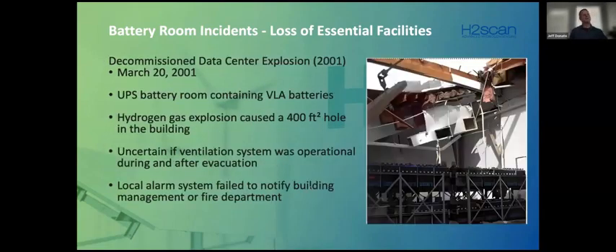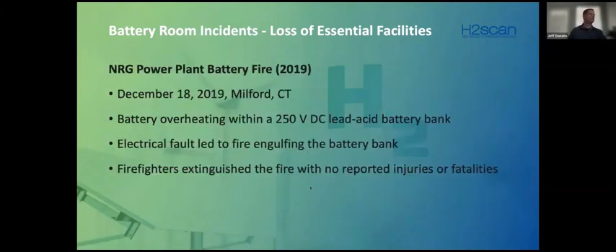Now, going back to this, there is a standard, NFPA 76, that has been written into the battery model codes. It basically says that you cannot have a hydrogen detection system that simply enunciates an audible alarm in a room and is not monitored by some sort of monitoring facility, fire panel, or building management system. Whenever you have any kind of safety device, like a gas detection device, it is supposed to enunciate somewhere, so that it goes to a central monitoring station, so that a ticket can be opened or action can be taken on that site.